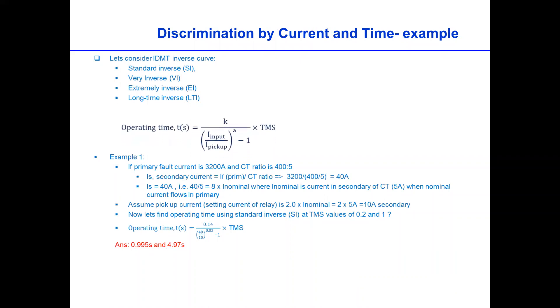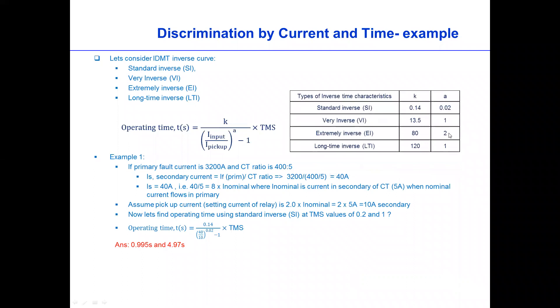So if we look now on this discrimination by current and time. If we consider we have IDMT curves and then we have an equation. So using this equation and this parameter provided, if for example in example one, if the primary fault current is 3200 amp and the CT ratio is 400 to 5 amp, then the secondary current can be calculated which is 40 amp and IR is 8 times the nominal current where the nominal current is 5 amp. So 5 times 8 is 40.